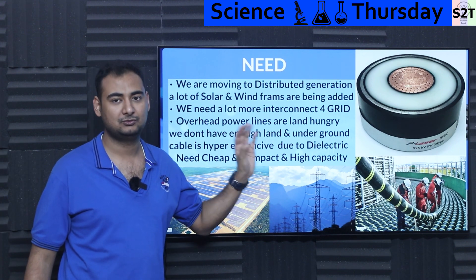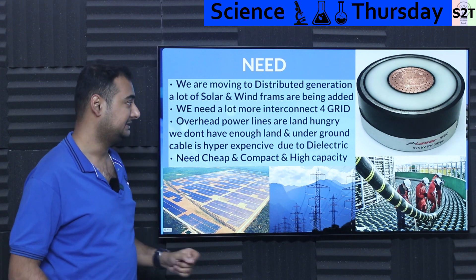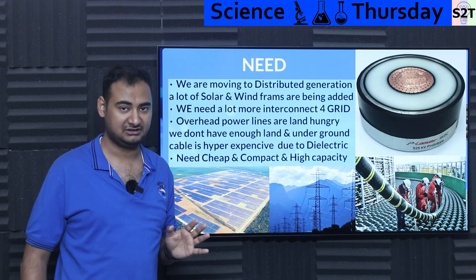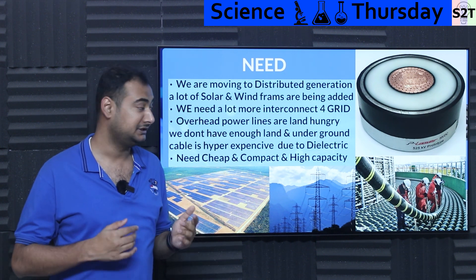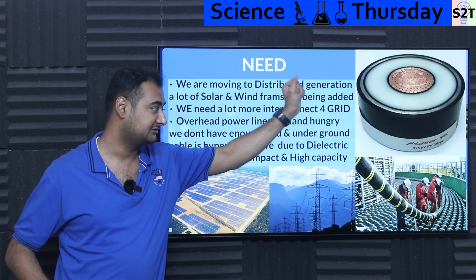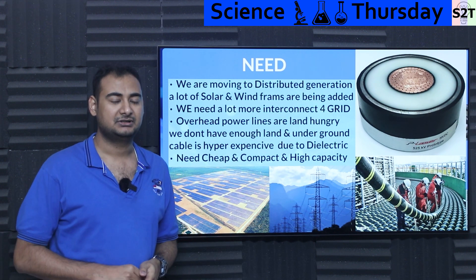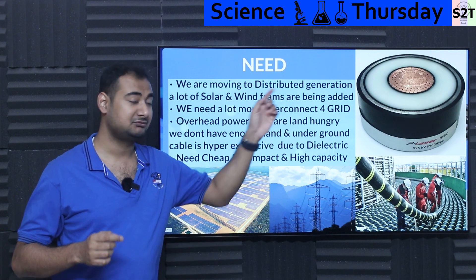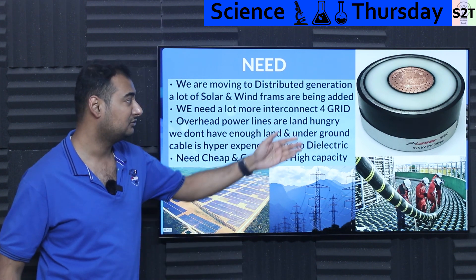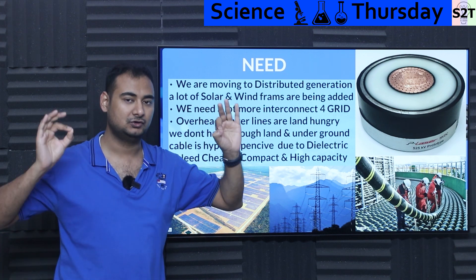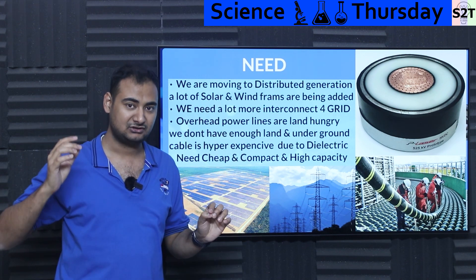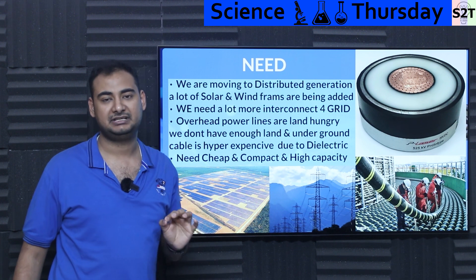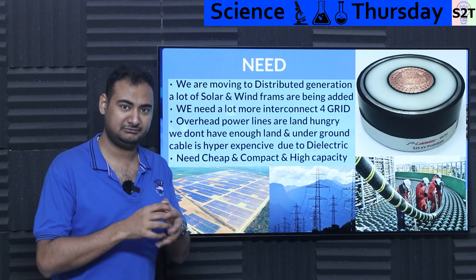Nobody wants to do underground AC if they have a choice — it's the worst option, not the first choice. What about high-voltage DC lines? No capacitance loss — awesome. No range limitation — super awesome. But the cost is extremely high. The dielectric strength required means the insulator thickness is directly proportional to voltage. For 500 kV it's this thick, but for 1,000 kV it becomes super thick and expensive. It has to be absolutely void-free while extruding — any minor defect equals a catastrophic failure.